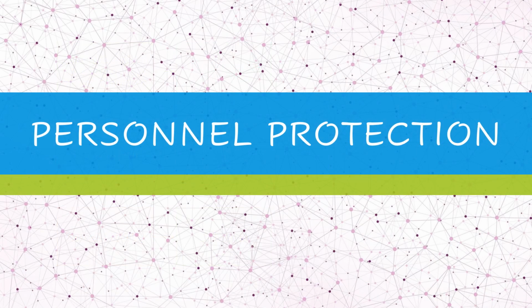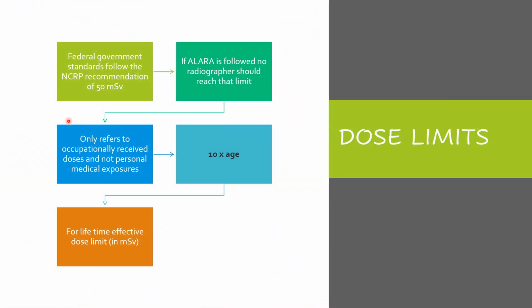Let's talk about personnel protection. So, dose limits. Federal government standards follow the NCRP recommendations of 50 millisieverts. If ALARA is followed, no radiographer should reach that limit. It only refers to occupational received doses and not personal medical exposure. For a lifetime effective dose, the limit is 10 millisieverts times age.